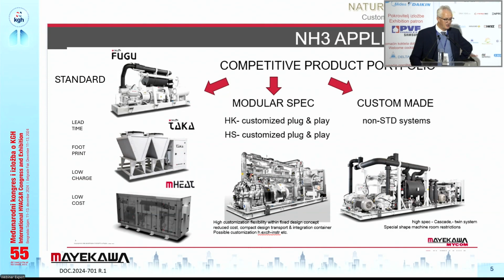Now, the bottom one, we call the M-heat. This is a product which is still, if you consider the technology readiness level of the product, where you have the 3 phases, you have the research, the design, and you have the practical application in the field, starting from a labo operation up to a continuous operation. This is a heat pump with ammonia, and it produces 1,500 kilowatt hot water, 90 degrees per hour. And the COP is around factor 5. So we have the case of 1,500 kilowatt output, 90 degrees, and your motor absorbed power will be below 300 kilowatt. And it is the plan to have it available the second half of 2025, also from stock.